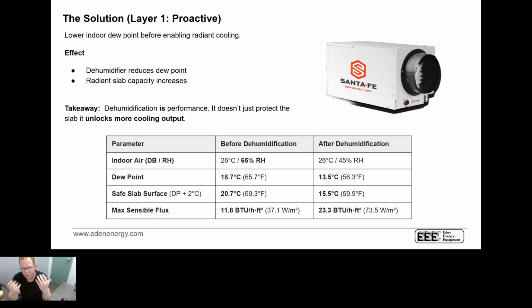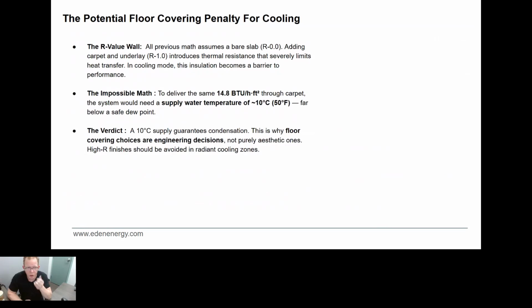But the nice part about this is what we're focused on here is lowering the indoor dew point, which is going to allow us to do radiant cooling that will take care of the entire load, because we're going to reduce the humidity in the space, which is going to increase the slab capacity by up to 35%. So as we reduce the humidity, what it means is we can now deliver a much cooler temperature into the slab, and we can go from 11 BTUs per square foot up to 24, 25 BTUs per square foot, because we no longer have that concern of what's going to happen. Is the floor going to sweat? Is it going to be a problem?